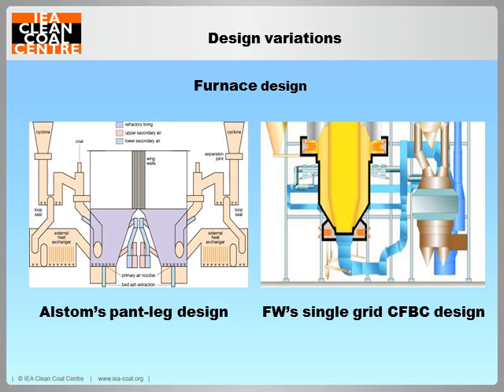Foster Wheeler's CFBC furnace, however, has one single fluidizing grate, under which there are several separate air plenums introducing primary air to the furnace. The primary airflow through the air plenums is individually measured and controlled to ensure equal airflow to all sections of the grate and uniform fluidization.